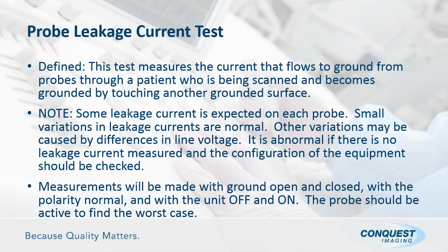Measurements will be made with ground open and closed, the polarity normal, and with the unit off and on. Now, notice the difference here. On the system, we had to do polarity normal and reverse. As far as probes are concerned, all we have to do is polarity normal. So it does remove one of our conditions. We have to do it with it off and on, open and closed, but only with the polarity normal. So it does remove that condition.